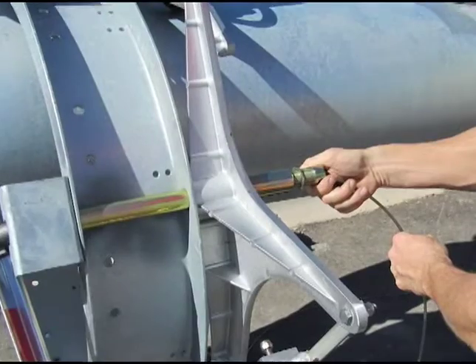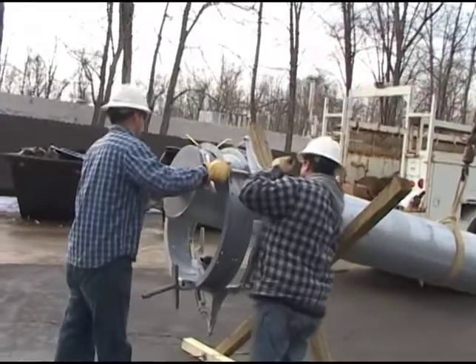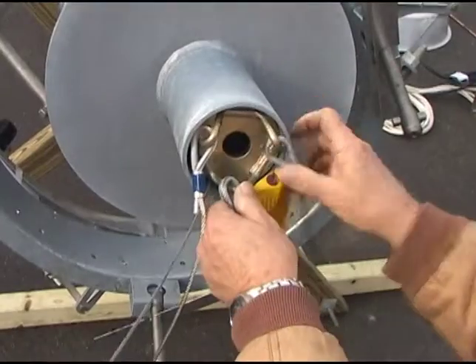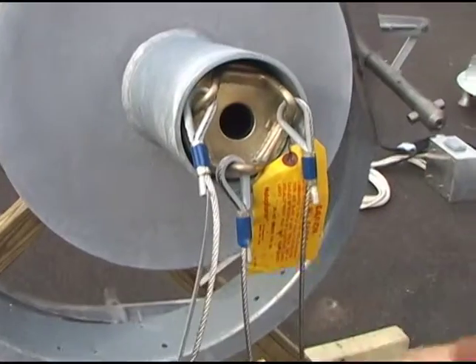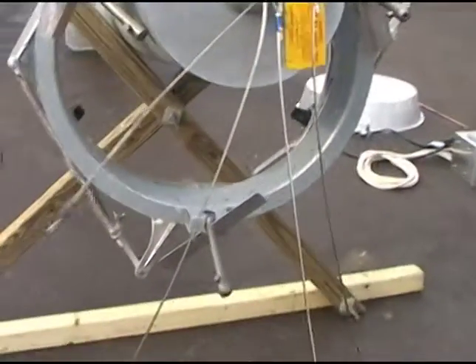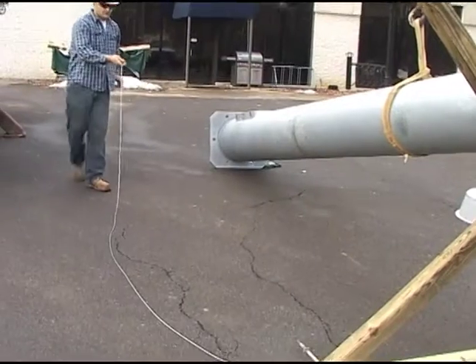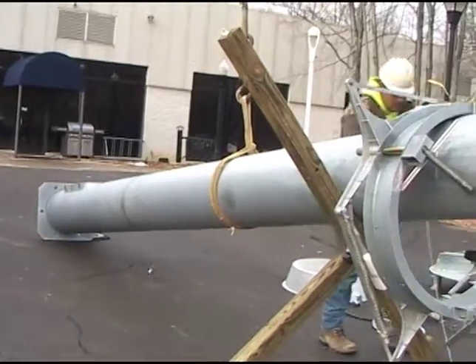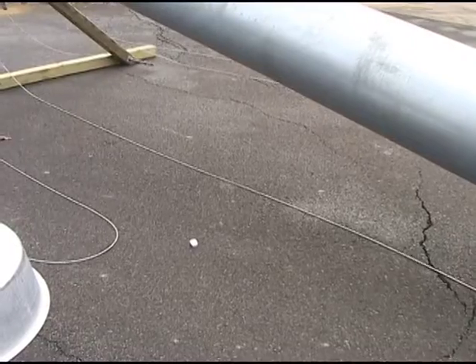The iris-type guide arms are oriented toward the bottom of the pole. Position the strain relief mounting hole upwards and in the center on the handhole position for alignment. Position the clevis assembly with the attached hoisting cables in the tenon opening with the 3 cables associated to the adjacent pins on the ring. Uncoil the power cord halfway down along the pole and back to the top. Uncoil the cables, hand over hand, without twisting, laying them alongside the pole. Be sure to uncoil in a manner that will not leave the cord twisted.